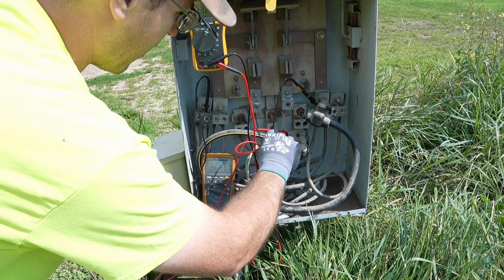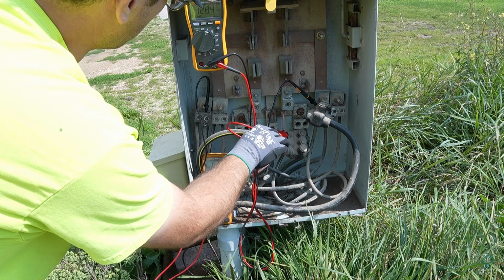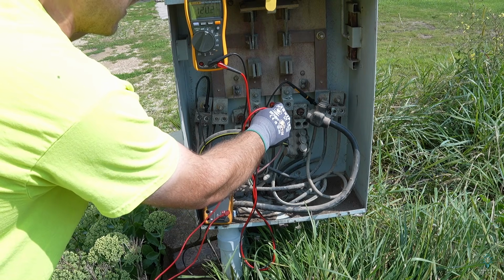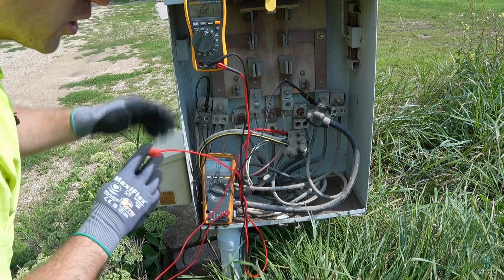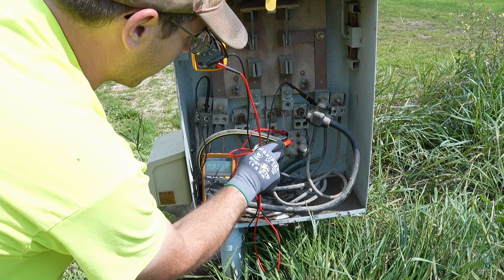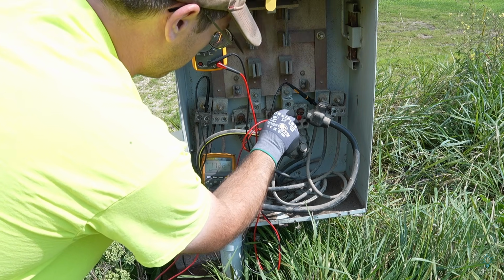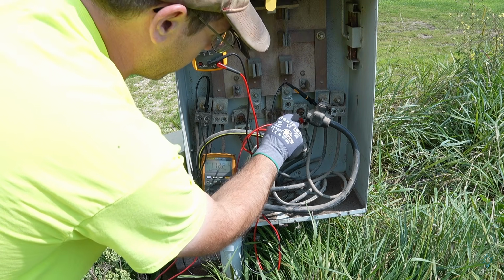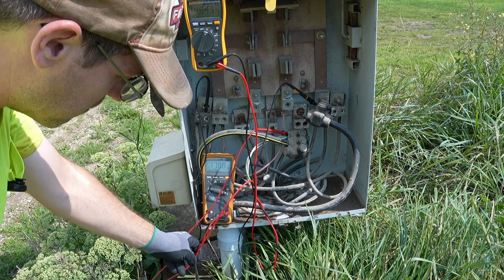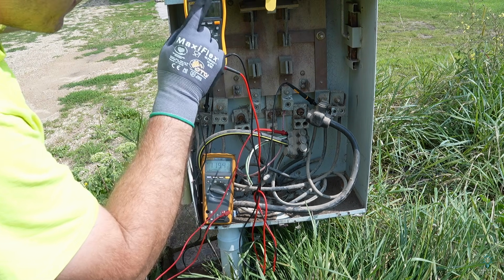So I took this top meter, and instead of going from here, we have 128 volts, but right to the actual neutral bar, we have exactly 120 volts, just like we are supposed to. So somewhere between right here and right here, we are losing that voltage. My guess is that very corroded point right there. That actually looks like the most corroded neutral point in this entire panel. So that to me is more than enough information to say that that is where the voltage drop issue in the house is coming from.